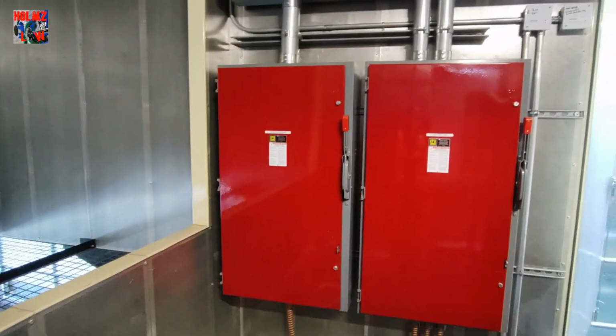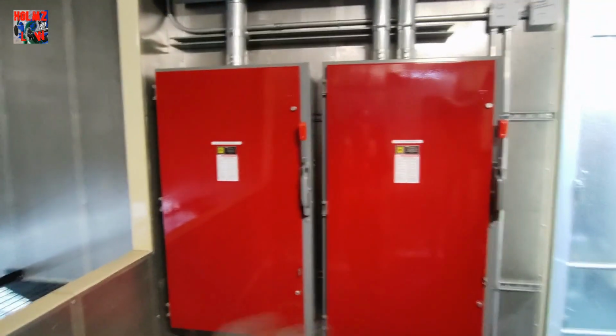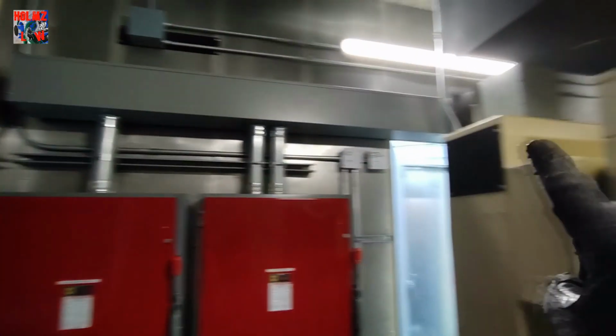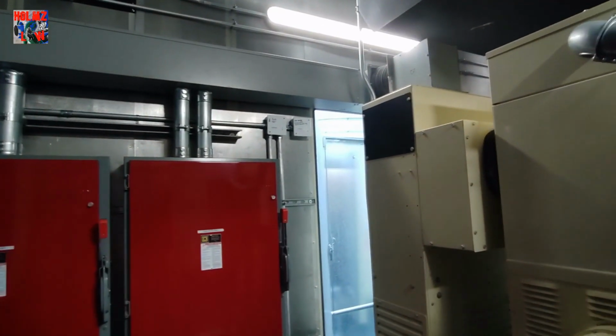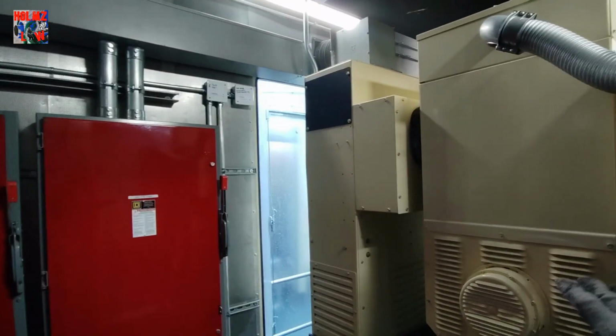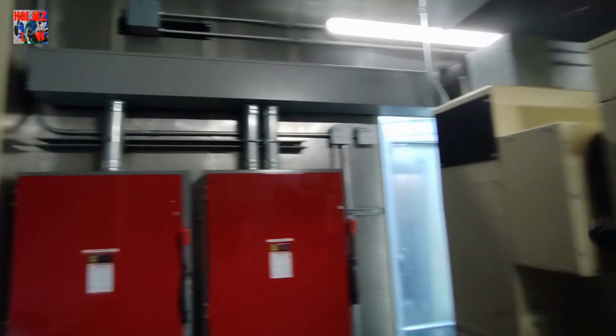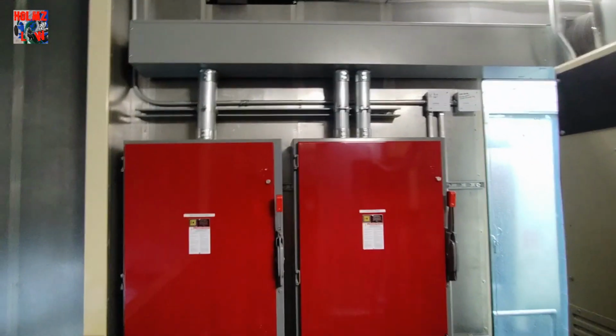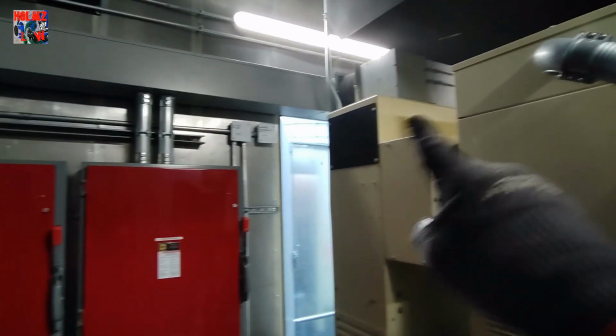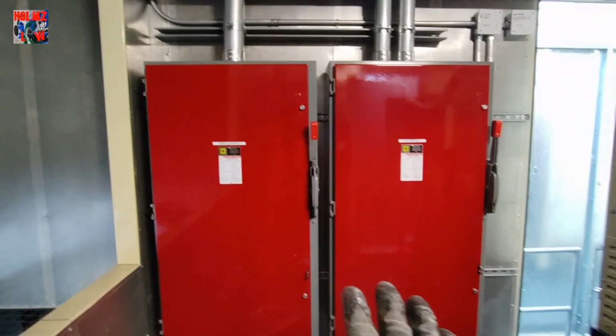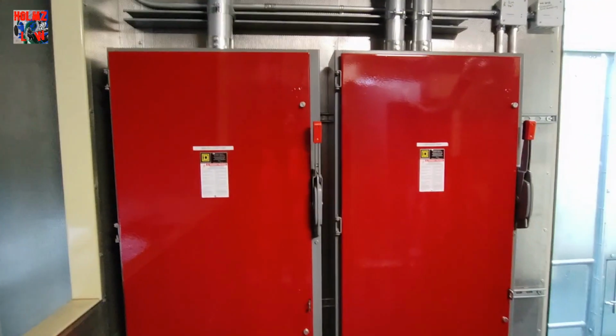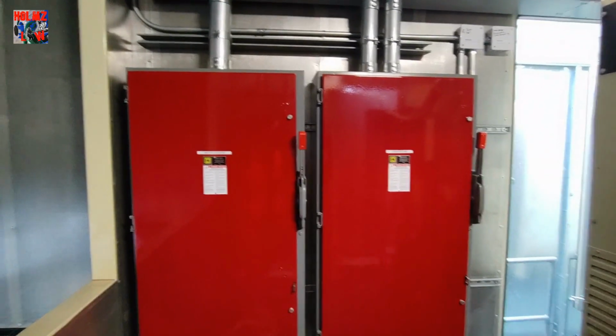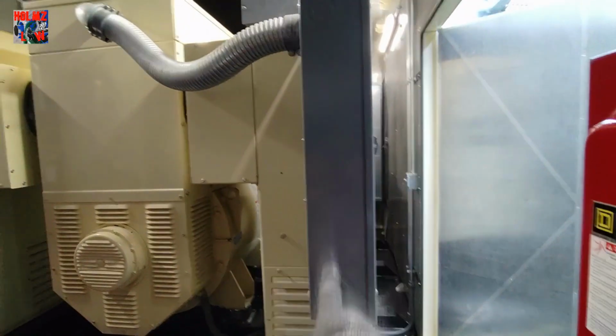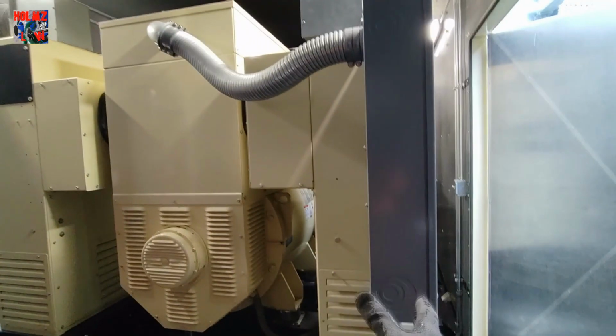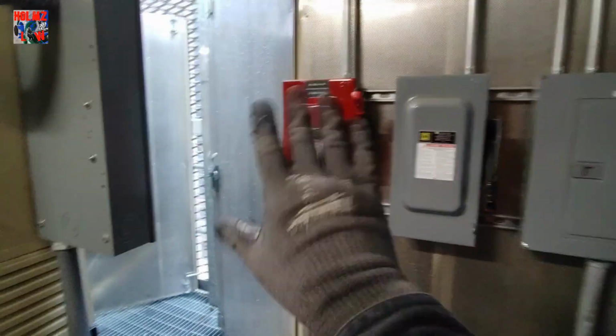Now, these here are two disconnects that are feeding the actual fire pumps. As you see, they ran wireways. Now, this was all prefabricated from the contractor that got the actual generator from Kohler. There was another contractor that actually did all of this enclosure. We just wired it. So, as you see, there's a wireway and it's feeding these two disconnects. These are actually feeding the emergency side of the fire pump through an automatic transfer switch as well as a controller. This enclosure here is doing the emergency side of all the loads on the emergency circuits. And this is the feed for the actual fire alarm.